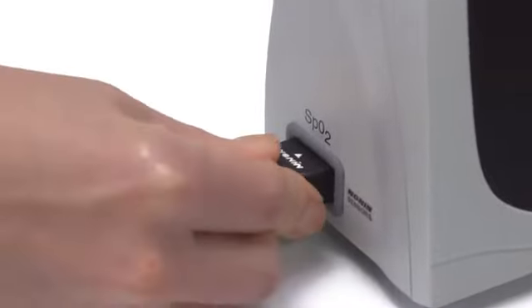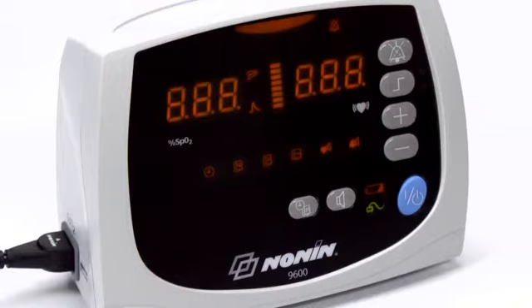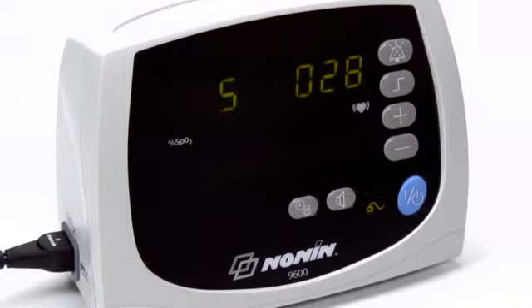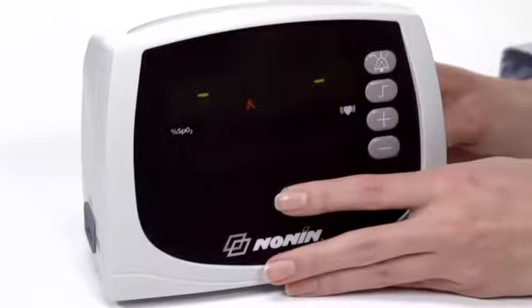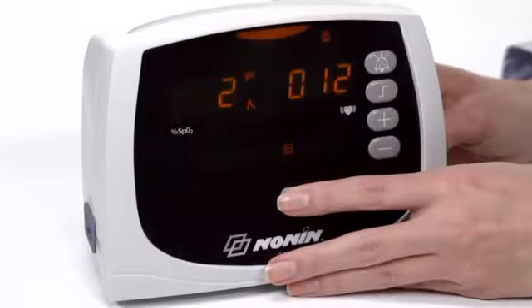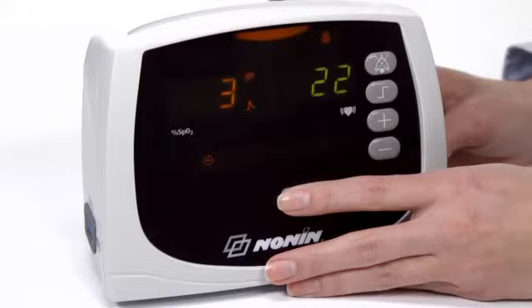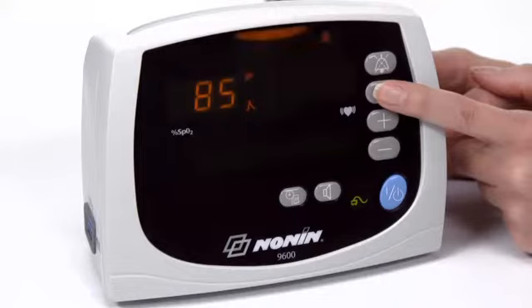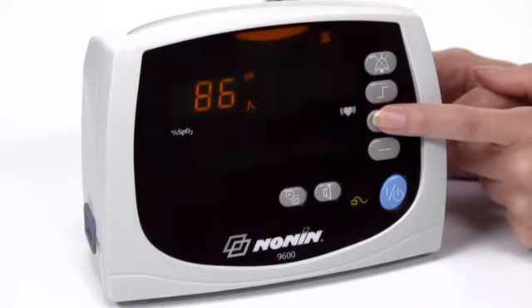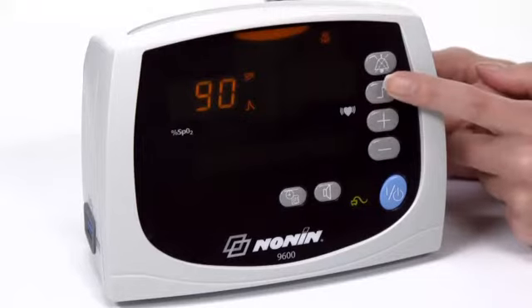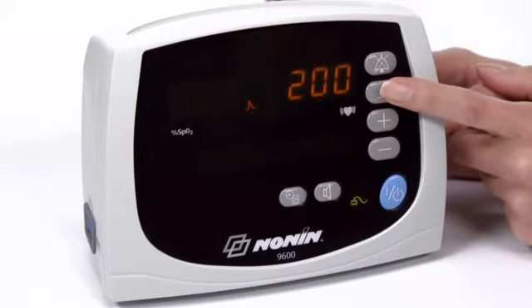Press the on-off button to start the unit. The oximeter will run through a startup check as it turns on. Check the oximeter's time and date settings for accuracy. You can set the time and date by pressing the clock button and using the scroll buttons to set the proper time and date. Alarm ranges can be customized by pressing the Alarm Limits button and then using the plus or minus button to scroll to the desired setting for each limit. Alarm limits will return to the default settings when the oximeter is restarted after being turned off.